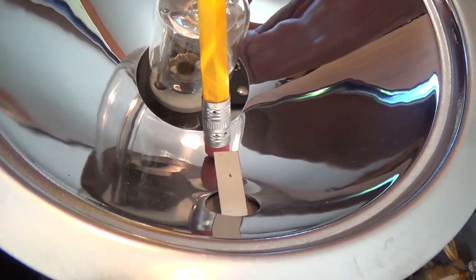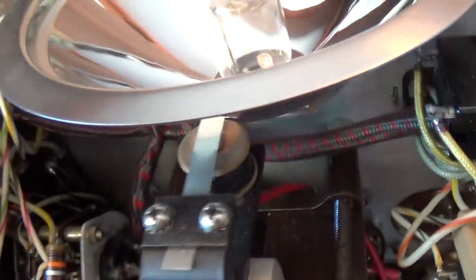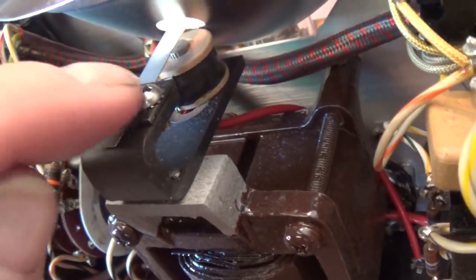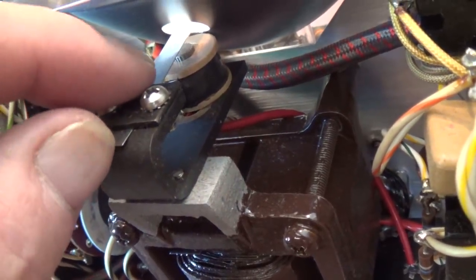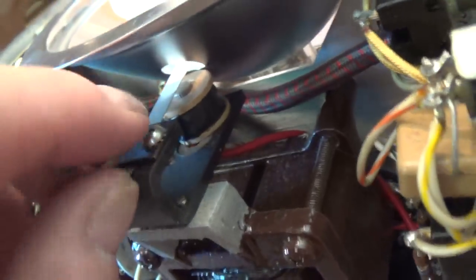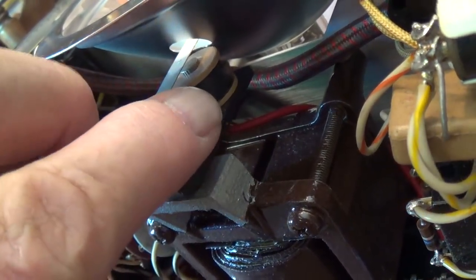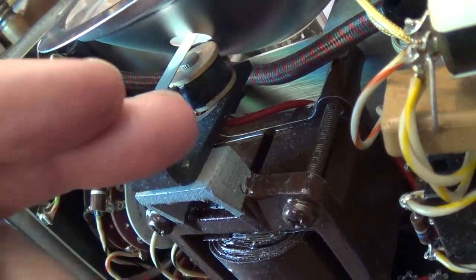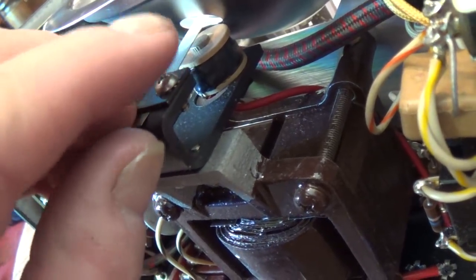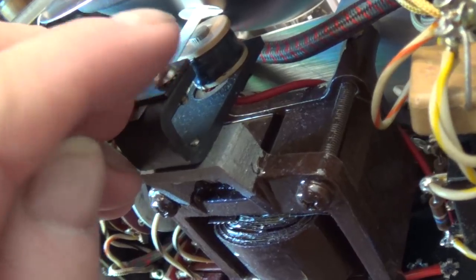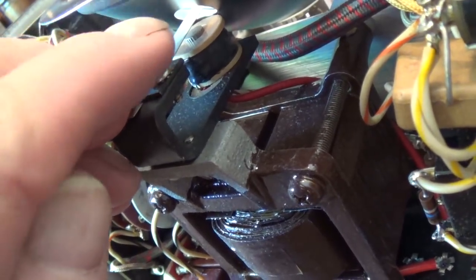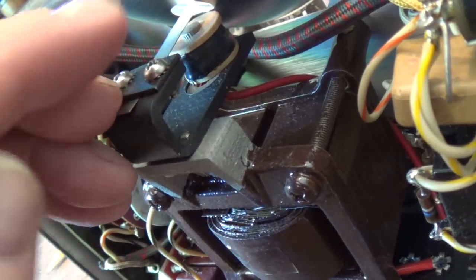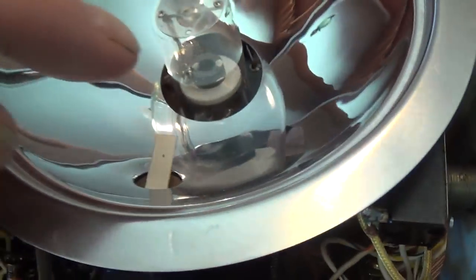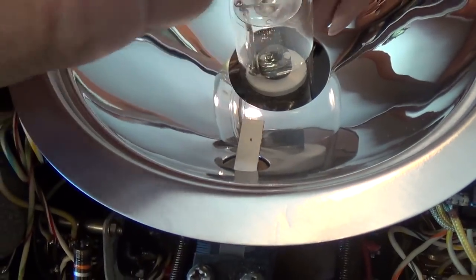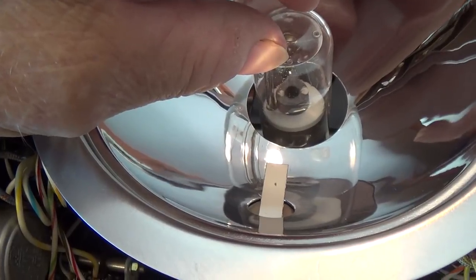Here we can see that little leaf that we use for calibration purposes, and if we look underneath here we can see exactly how it works. One end is anchored here, I guess so that you can replace the leaf if it wears in the middle here and breaks. But look, a coil here that is connected to the wall current, and therefore the polarity in the coil will vary 60 times per second, which will attract the leaf and repel the leaf at exactly the same rate. So the little leaf is going to vibrate back and forth 60 times per second, or 3,600 times per minute. And we will use it here because this will strobe on the leaf. We can use it then to calibrate the rate of the strobe.